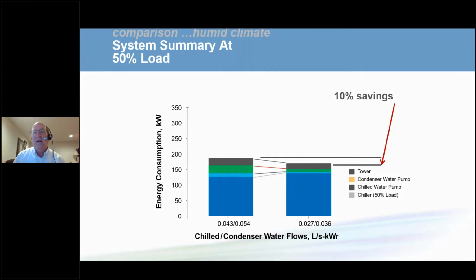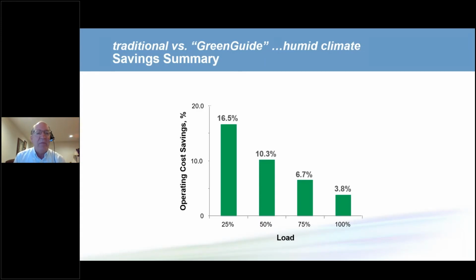In fact, if we look at it at different operating times during the year, we see that the savings are between about just under 4% to almost 16%. Now I tell people, be really careful when other people share percentages, because 16% seems like a lot, but remember that's when the system's operating at 25%, and that's going to be less power. But overall, from a yearly annual standpoint, the system energy usage is lower.